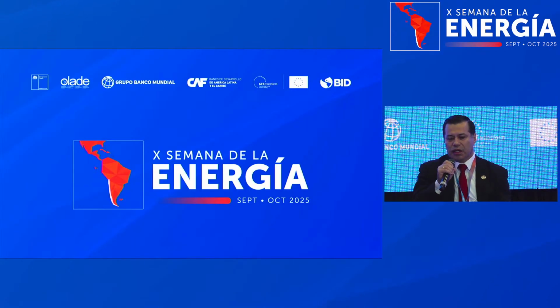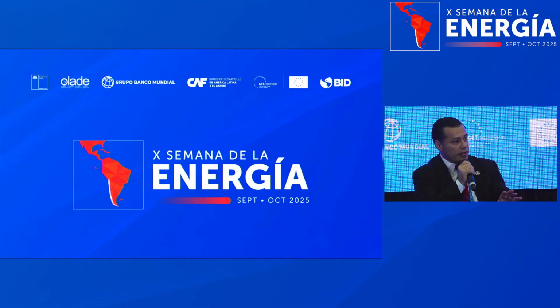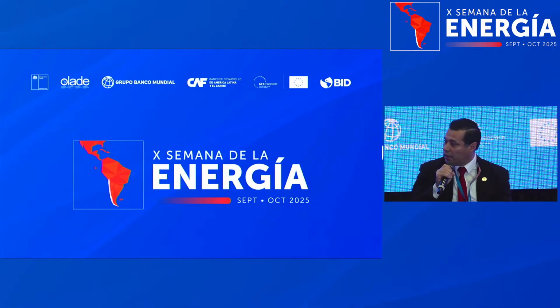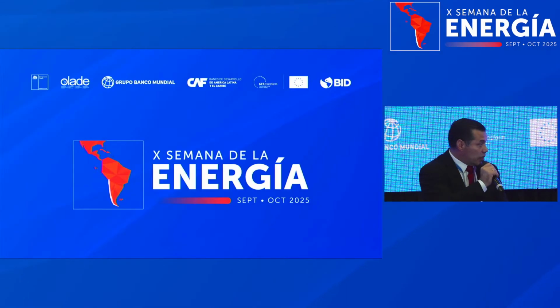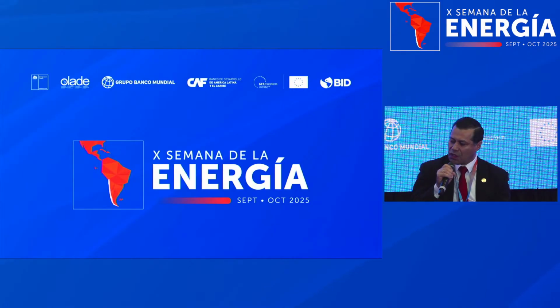On one hand, there are certain dates where you're allowed to disconnect. So we have defined in the contract itself that we can disconnect up to 90% of the demand, just by sending a request 10 minutes before disconnecting, if the demand is growing too much. And if there is a need of the system as well, it has to disconnect up to 90 minutes depending on the demand. There's an operational center where the whole system can be disconnected automatically. This disconnection can amount to up to 350 hours on a yearly basis. This allowed us to manage this demand level, which I repeat, is 18% of the interconnected national system at the moment. So it allows us to optimize our electrical infrastructure.